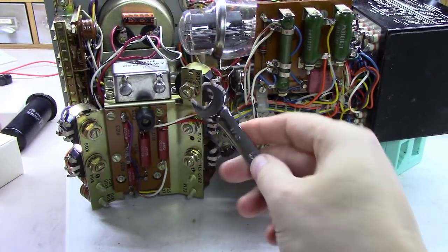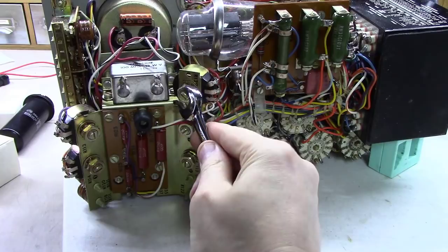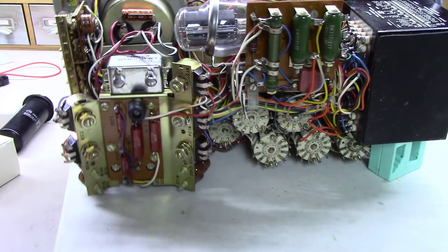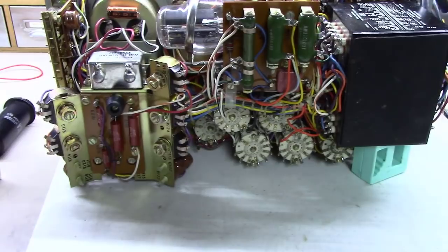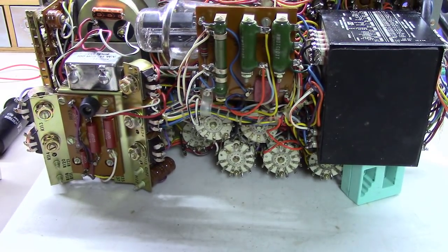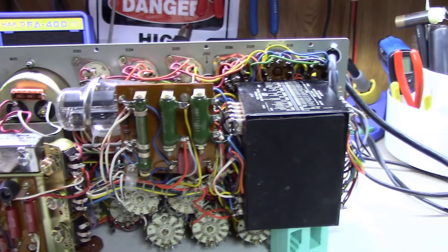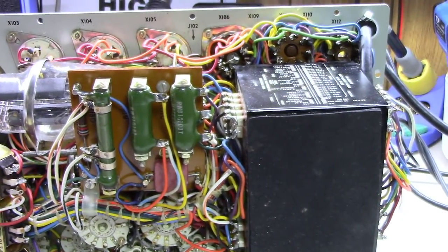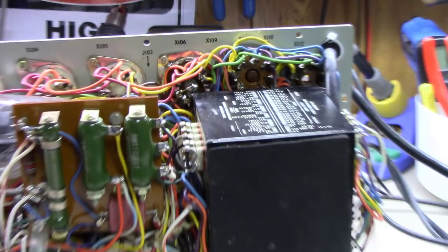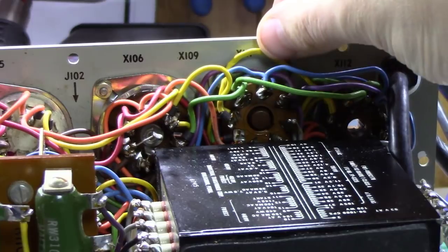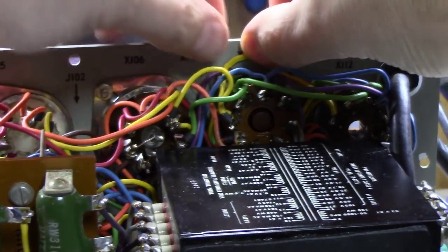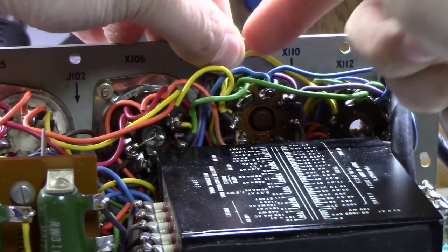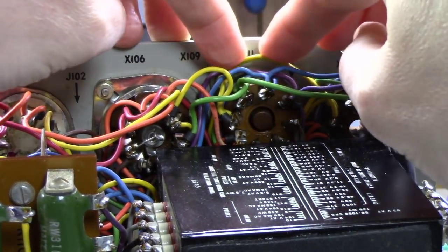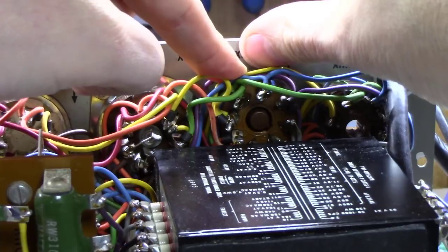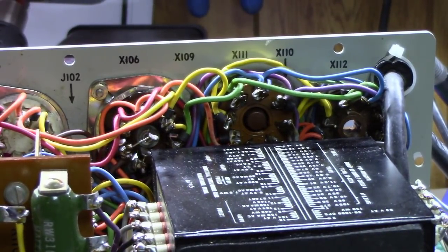Okay, at this point I've just used a 1/2 inch socket here, and I've gone through and tightened all these lock washers up really good. Made sure all the screws here are good and tight on this thing. You need to go around and look for any pinched wires, and let me show you exactly what I'm talking about. This unit actually has one. I guess they were either done this way a lot from the factory, but you can see this one as it was closed. Right there is where it sat, and then when this thing dropped down inside the chassis, you can see how flattened this thing got. So I'm going to have to get that wire out of the way so that when the lip of the chassis comes down in here, it doesn't pinch a wire.